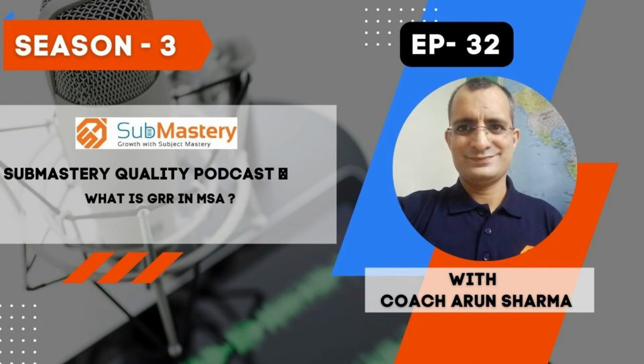So if you look at this particular word, GRR, what does it mean? What's the meaning of that? So we'll try to understand this. GRR stands for Gauge, Repeatability and Reproducibility. This term defines that you need to identify the variation which is there in the measurement system, and the variation is basically in two areas. What are those two areas? One is repeatability, other is reproducibility.